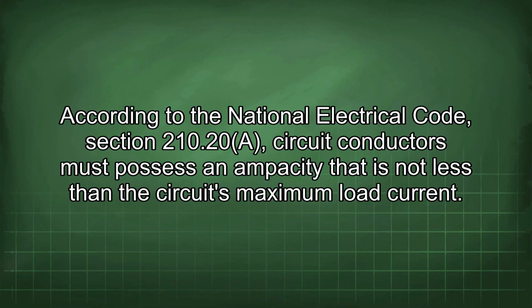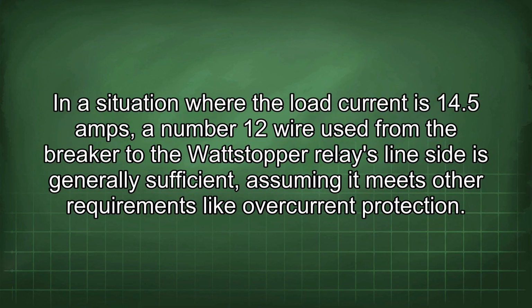According to the National Electrical Code, Section 210.20(A), circuit conductors must possess an ampacity that is not less than the circuit's maximum load current. In a situation where the load current is 14.5 amps, a number 12 wire used from the breaker to the Watt Stopper relay's line side is generally sufficient, assuming it meets other requirements like overcurrent protection.